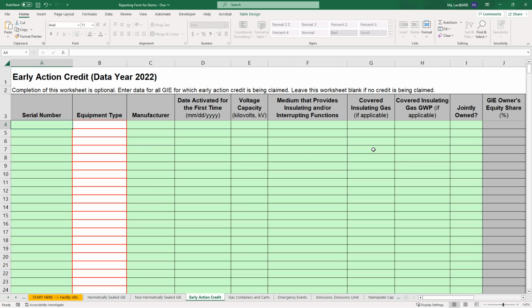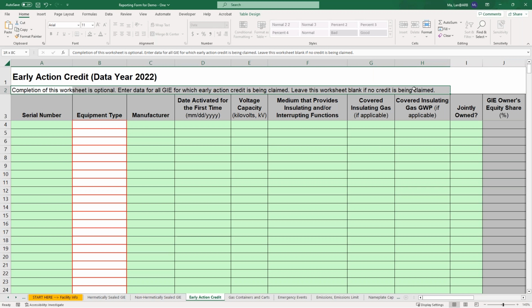As noted at the top, completion of this tab is optional. Per section 95353D, regulated entities may accrue early action credit starting in 2021 for each circuit breaker that meets the following criteria. First, it must have been activated for the first time between January 1st of 2021 and the phase-out date for an equivalent SF6 GIE device. Second, it must have a voltage capacity of 72.5 kV or greater. Third, it must not be insulated with SF6 or oil.